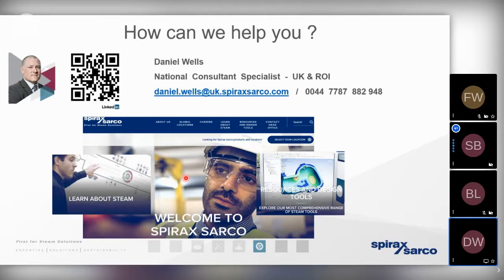So we've got a question from Daniel, and he says, "Good afternoon. We have a boiler operating at around 7.5 bar. I presume that's bar gauge, which is then reduced at a pressure reducing station to 5.6 bar for network distribution. Why is this done? Is this to do with latent heat, etc.?" So just a quick explanation again about pressure reduction there. Yes, it'd be interesting to know where the pressure was reduced.